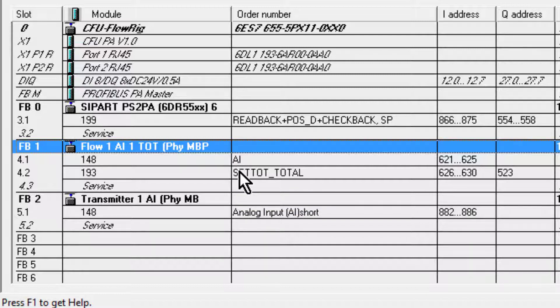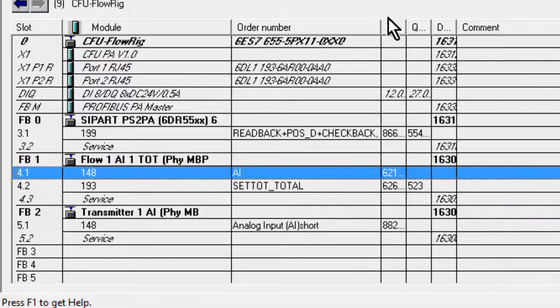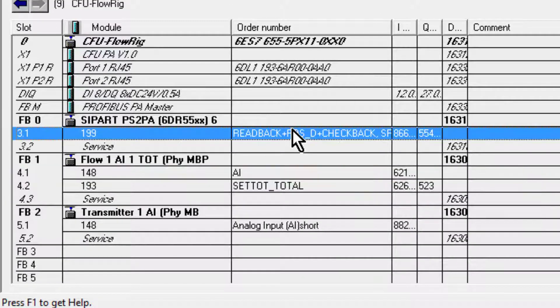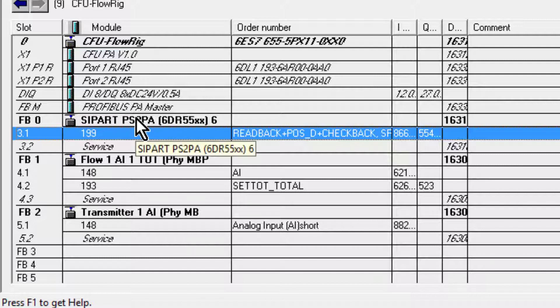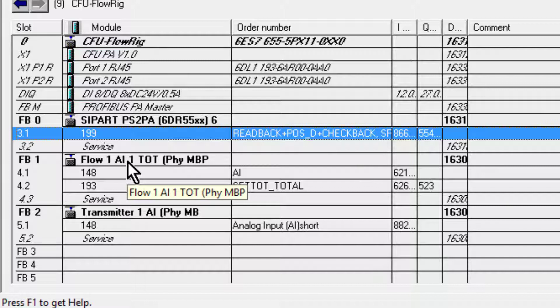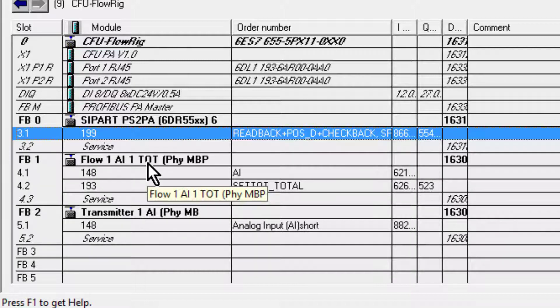As long as it's Profile 3 or above, it will communicate to this memory location. You can mix on the same card - this device here is using a manufacturer-specific GSD and this one is using a profile-specific GSD, so I can have a mixture on the same card.